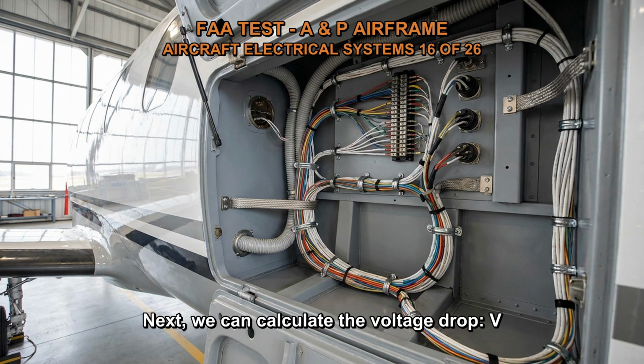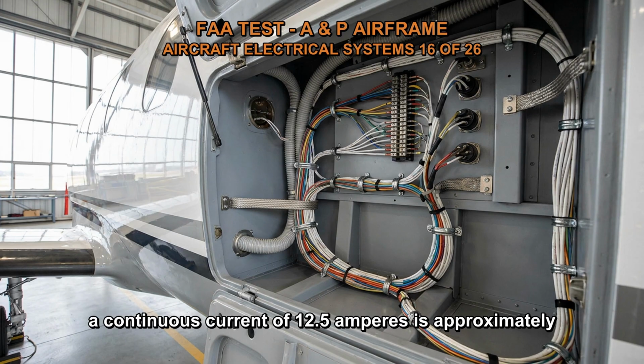Next, we can calculate the voltage drop. V = I × R. V = 12.5 amperes × 0.313 ohms. V is approximately 3.913 volts. Therefore, the voltage drop for a number 18 copper wire that is 50 feet long and carries a continuous current of 12.5 amperes is approximately 3.913 volts.